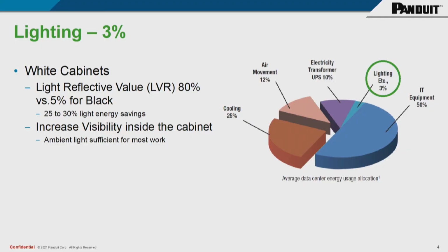I've taken the middle of the road—would you believe 80% is the middle of the road? Well in this case it is. If you look at the luminescence or light reflectance from various surfaces, white cabinets are definitely the solution to employ when looking at a comms room fit-out. Whether you're hot or cold aisle separation, cold aisle containment, hot aisle containment, or down to a VED—vertical exhaust duct or chimney—comparing white to black you could see a 180% improvement in light illumination compared to a black cabinet. So it's absolutely a no-brainer to work with the lighter colored reflective surfaces.